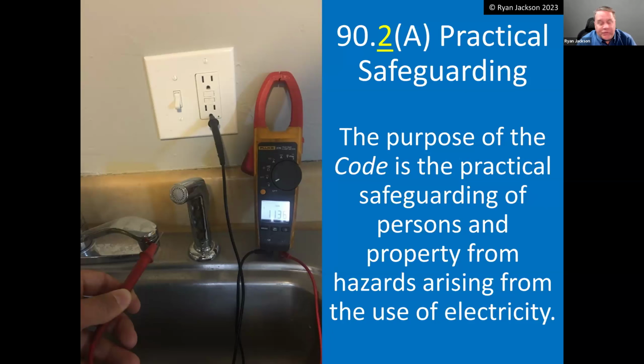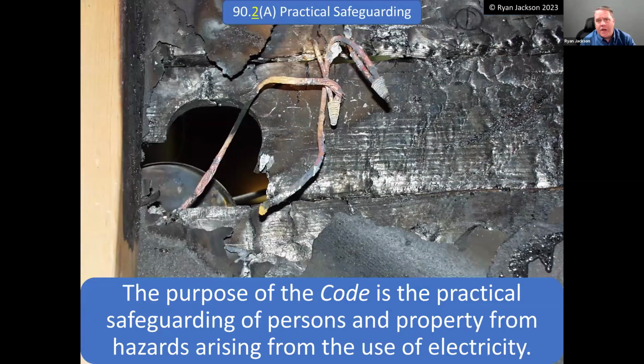Believe it or not, there were about 15 fatalities during the Gulf War from miswired barracks that resulted in a very similar installation like this. There were about 15 of our soldiers that in the barracks went in to take a shower at different buildings, different times, and ran into the situation and perished from it. So as bizarre as this is, it's not Photoshop. This is a real thing, and if you screw up badly enough, you can create a situation like this and end up killing somebody. And that's why the code exists, right? The whole reason the code is there is to protect people from what? Electric shock and from fire.